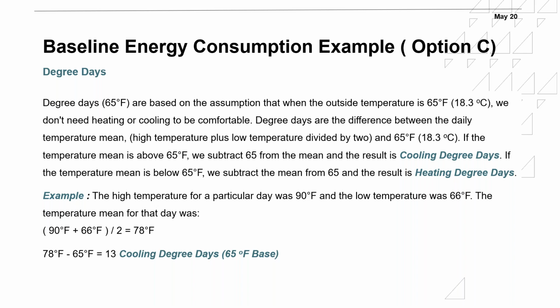So degree days are the difference between the daily mean temperature, which is the high temperature plus the low temperature divided by 2, and 18.3. It's a subtraction of the two. If the mean temperature is above 65, we subtract 65 from the mean, and the result is the cooling degree days. If the mean temperature is below 65, we subtract the mean from 65, and the result is the heating degree days. Meaning if the temperature is below 65, we'd need heating. Above 65, we would need cooling.